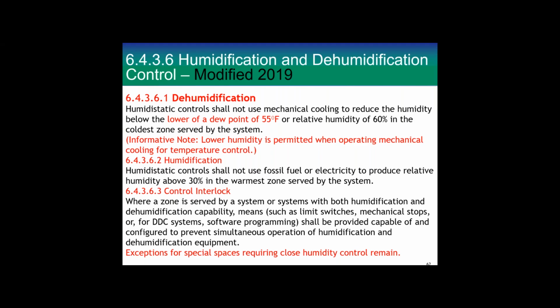So humidistatic control shall not use mechanical cooling to reduce the humidity below the lower of a dew point of 55. That's the normal dew point for supply air. Many standard designs would supply air at 55 degrees, so your dew point comes naturally there. Or a relative humidity of 60% in the coldest zone served by the system. All that means is if you're just going to dehumidify, and there's no other reason to do it, we don't want you to reduce the air temperature lower than 55 just to do that. You could have some other reason to knock it down to 53, but just to remove humidity, without the exceptions, we don't allow you to do it.